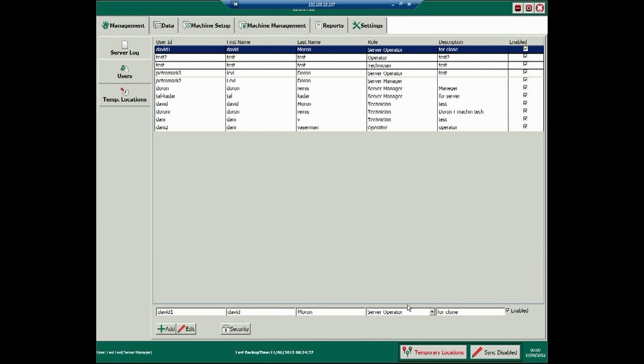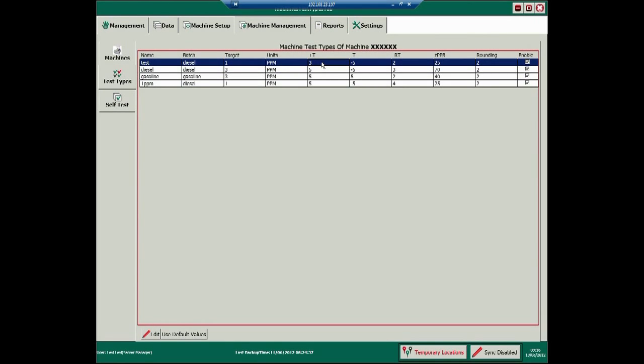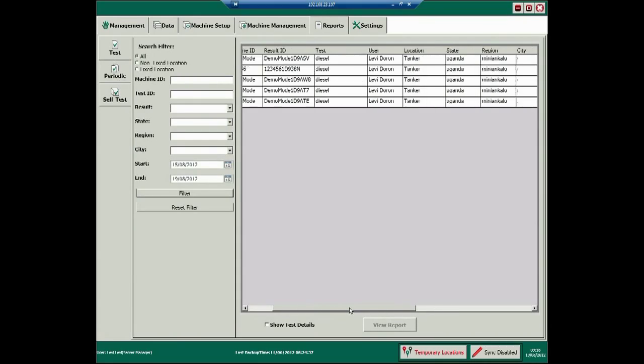The server administrator sets all parameters and specifications, such as users' privileges, type of analytical methods, result criteria for pass and fail, and identifies the analyzer systems with their location. Each change creates an update on every system, making spread operation an easy task.